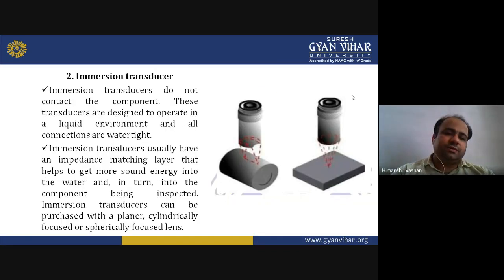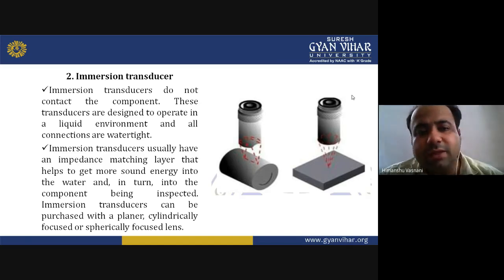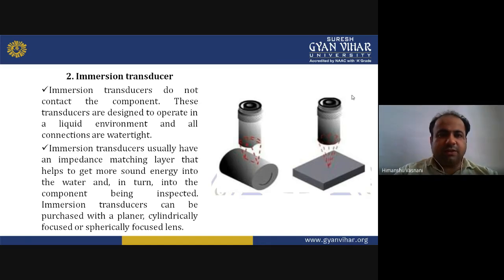Now, the immersion transducers. You can see in the diagram, as the name says, immersion, something is immersed in a liquid. So the immersion transducer does not contact the component. Irrespective of the previous contact transducer, this is immersion. These transducers are designed to operate in a liquid environment and all connections are watertight. They need to be watertight to avoid complications. When the environment is a liquid environment for operation, then obviously the connections are automatically watertight.